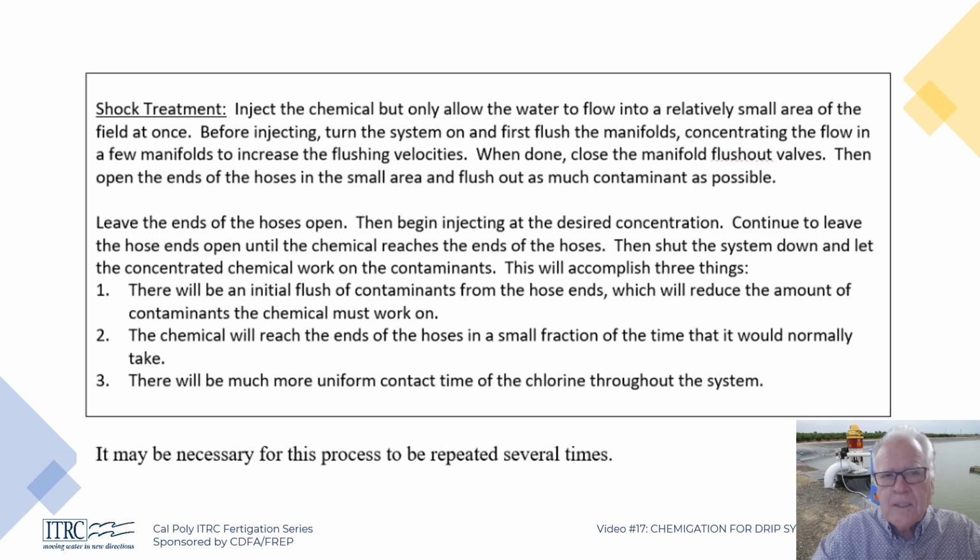Just so you know, a lot of the pipes have been reduced in diameter a little bit too much, and the water goes shooting out of the end caps or the end valves or whatever they have, and it looks like there's a high flow. All there is, is a high velocity, and it isn't really giving much of a velocity in the bigger pipes that are upstream. So you need to force the water through. So you've turned on part of the system, you've shut off the hoses, you've flushed the manifolds, and you meticulously go through the area and do this.